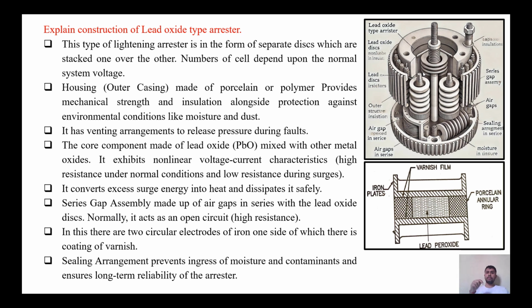Housing, that is casing made up of polymer or porcelain material, provides mechanical strength and insulation alongside protection against environmental conditions like moisture and dust. It has venting arrangements to release pressure during these faults. The core component is made up of lead oxide mixed with other metal oxides. It exhibits non-linear voltage current characteristics, that is high resistance under normal condition and low resistance during surges. It converts excess surge energy into heat and dissipates it safely into the environment.